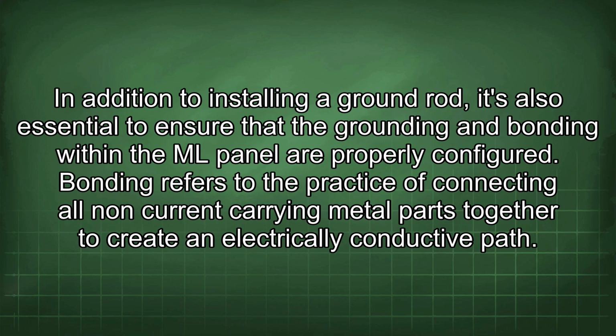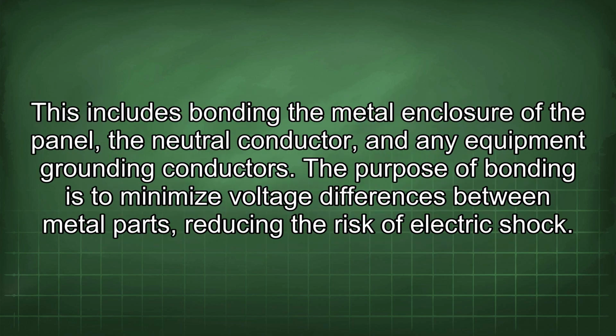In addition to installing a ground rod, it's also essential to ensure that the grounding and bonding within the ML panel are properly configured. Bonding refers to the practice of connecting all non-current carrying metal parts together to create an electrically conductive path. This includes bonding the metal enclosure of the panel, the neutral conductor, and any equipment grounding conductors. The purpose of bonding is to minimize voltage differences between metal parts, reducing the risk of electric shock.